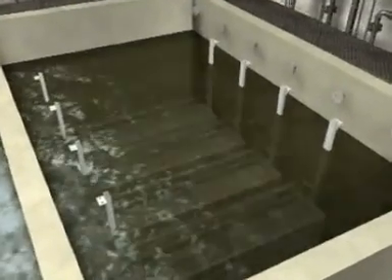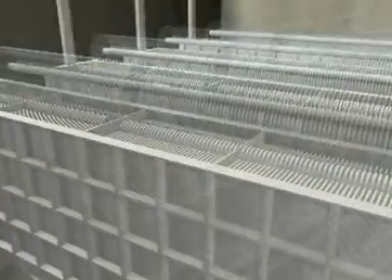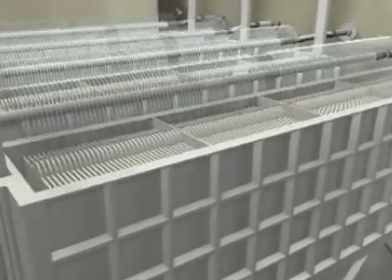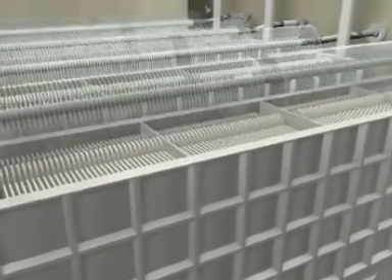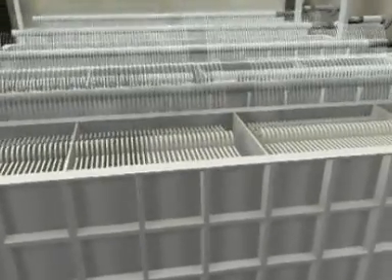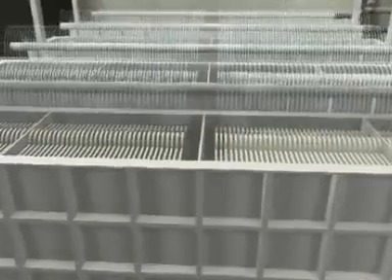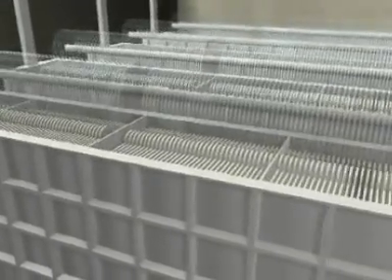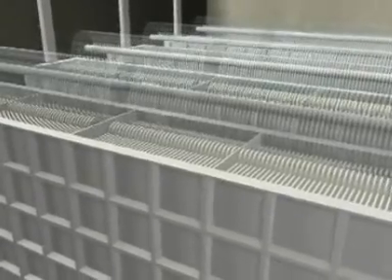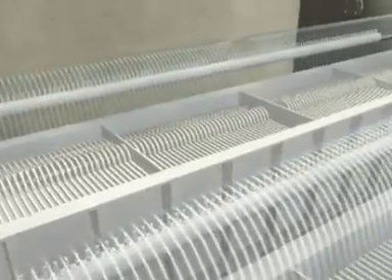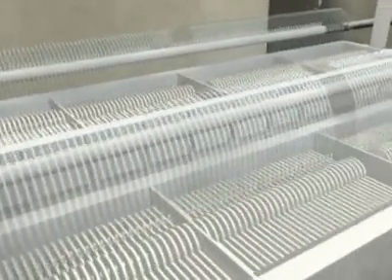Each membrane unit may contain up to 200 flat sheet membrane panels, the number of panels required being dependent on hydraulic flows and loads. Membrane bioreactors utilize the biomass contained within the mixed liquor to degrade the incoming pollutants, and the submerged flat sheet membranes to filter the treated permeate from that biomass. The combination of the high concentration biomass and the membranes produce a very high quality permeate. With the Aquatil Group's MBR technology, this quality is typically better than 5/5/5 biological oxygen demand, suspended solids and ammonia.